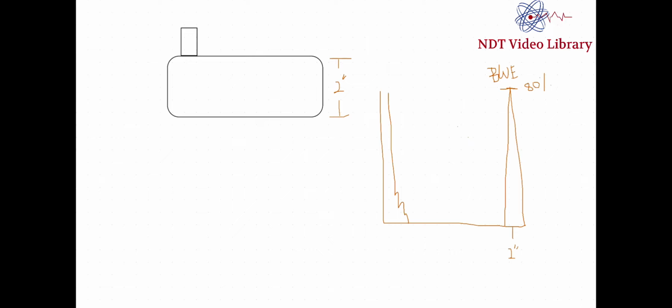Okay, first back surface reflection, back wall signal, back wall echo. All of those are correct. Not front surface. Okay. Someone mentioned front surface signal. Front surface signal is, this is the front surface on the top. The top part of the object is front surface. The bottom part of the object is back surface. So your front surface is your initial pulse when it's contact. You don't have a separate front surface when you're on contact.